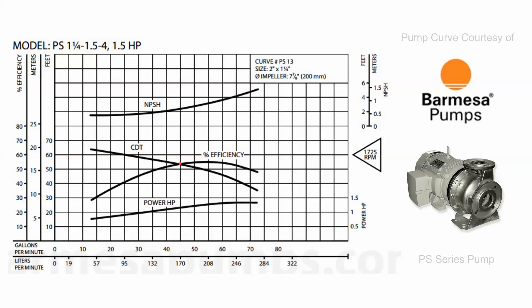In most cases a pump is designed around that middle point, and everything else is essentially a byproduct. You can see that in high head applications this pump is not very efficient. However, as we increase the amount of flow we're trying to push, thus moving more water per rotation of the pump's impeller, we increase the efficiency until we peak out at that best efficiency point, and then efficiency starts to decrease again.